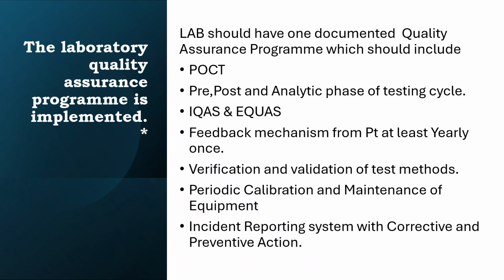Periodic calibration and maintenance of equipment is required for all the equipment. Some equipment requires 6-month calibration, some equipment requires 1-year calibration, so that needs to be defined in the manual. And for preventive maintenance, all equipment should undergo preventive maintenance every 6 months. Some companies provide it, and some the hospital side will do.